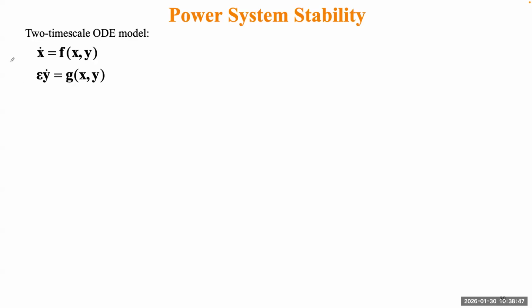So I use X here to represent the slow dynamics, focusing on the electromechanical behaviors of generators. Usually that time frame will be from maybe tens of milliseconds to several seconds. And there's also faster dynamics, mainly focusing on the electromagnetic transients, such as instantaneous voltage and instantaneous current of the network, and also some instantaneous variables inside the generator and controllers.